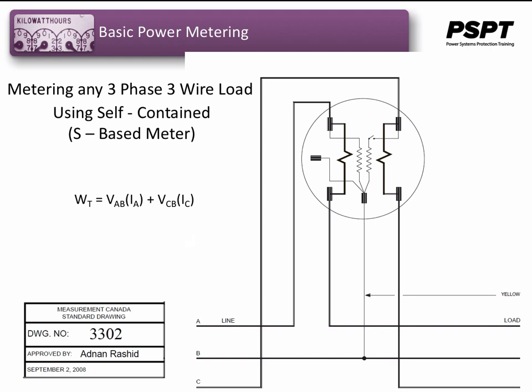And metering any 3-phase 3-wire load using a self-contained or an S-base meter, such as Measurement Canada here uses 3302, the first element would be on the left, the second element would be on the right, and measuring the same quantities as an A-base meter, which we just looked at in the previous slide.